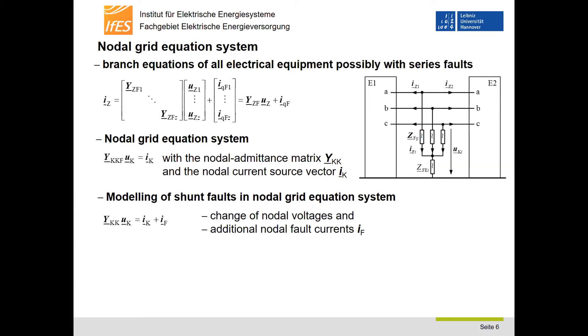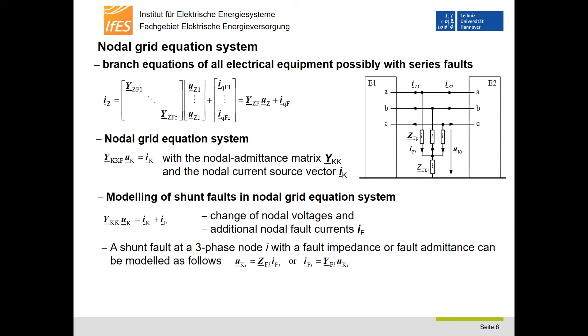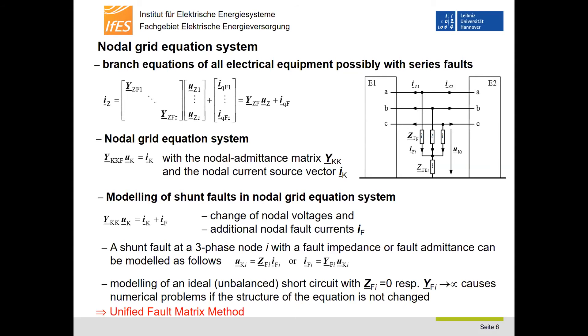Having a shunt fault, the nodal voltages change and additional nodal fault currents IF have to be considered. A fault impedance or fault admittance, modeling for example an arc resistance, can also be considered. With it, the relationship between fault currents and nodal voltages can be defined. Modeling of an ideal unbalanced short circuit with ZFI equal to zero, respectively YFI going to infinity, causes numerical problems if the structure of the equation is not changed. To overcome these problems, the unified fault matrix method offers also a solution.